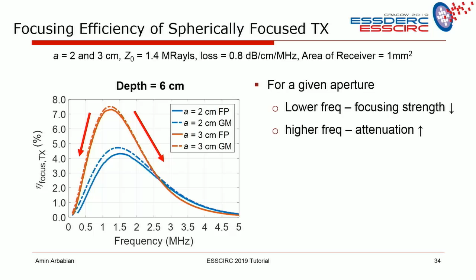And it comes from just the capability of focusing, capability of losses in tissue. Now, if you come up with an application that requires to go 1 centimeter deep with a 100 micron transducer, the optimal frequency is going to be very different. Here we're talking about millimeter size and going to 5, 10 centimeters in tissue. That's the optimal frequency range.